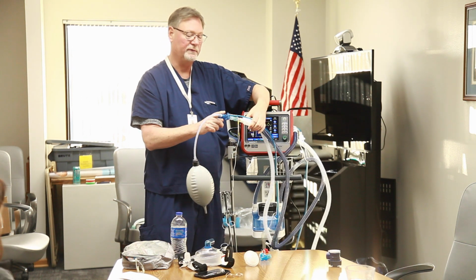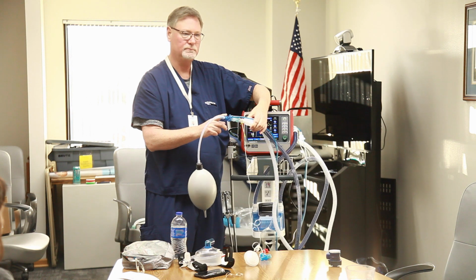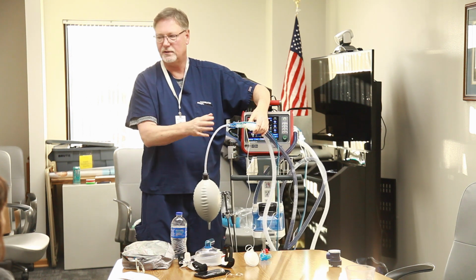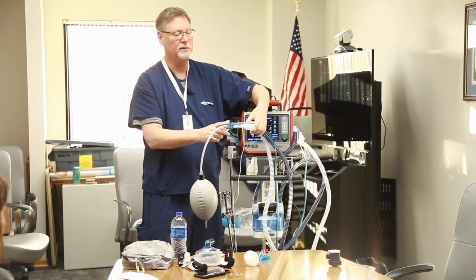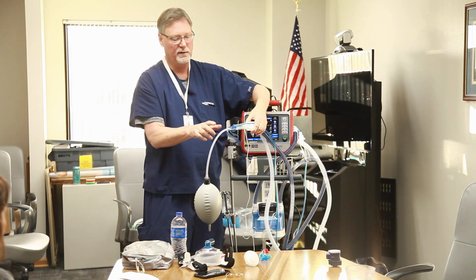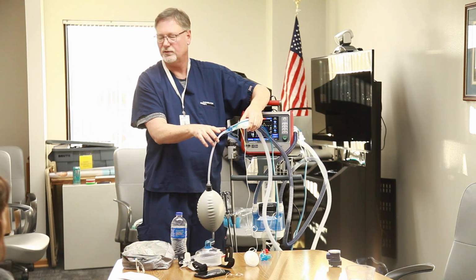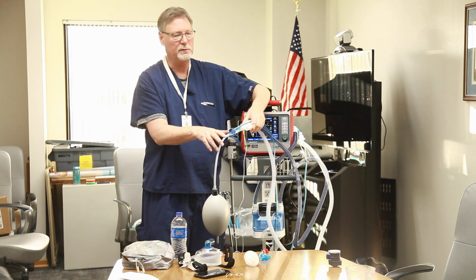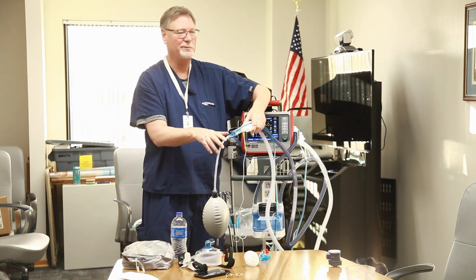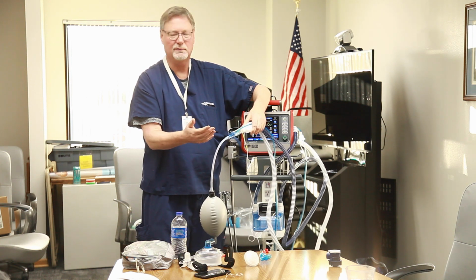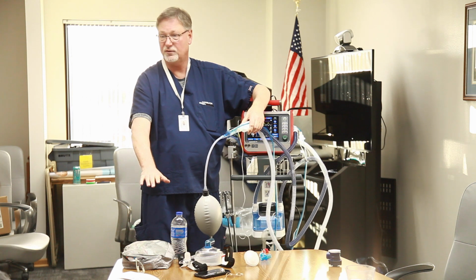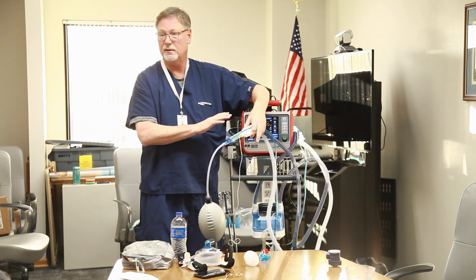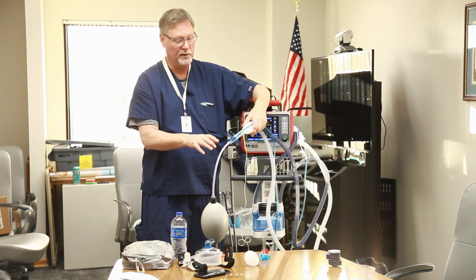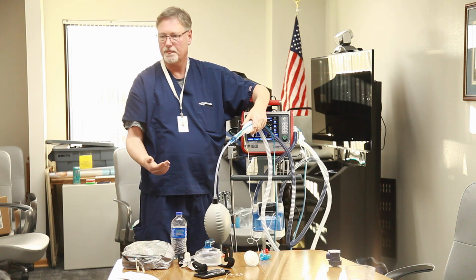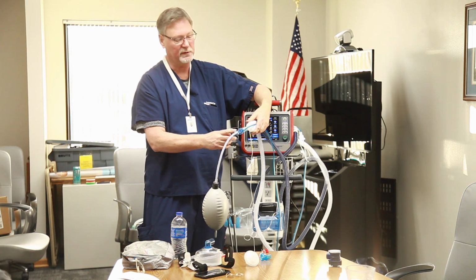Tidal volume is delivered right from this flow sensor. It's dead space no matter which side it's on, it doesn't make any difference, but I want to deliver the right tidal volume to the patient. If I have a bunch of dead space on this side, it's going to deliver less tidal volume. For everybody in this room, it doesn't make a difference, right? But if you get a small patient that you intubated that you want to put on this, and you don't want to bag them until they get here, it makes a difference. So that's where the tidal volume is delivered from.